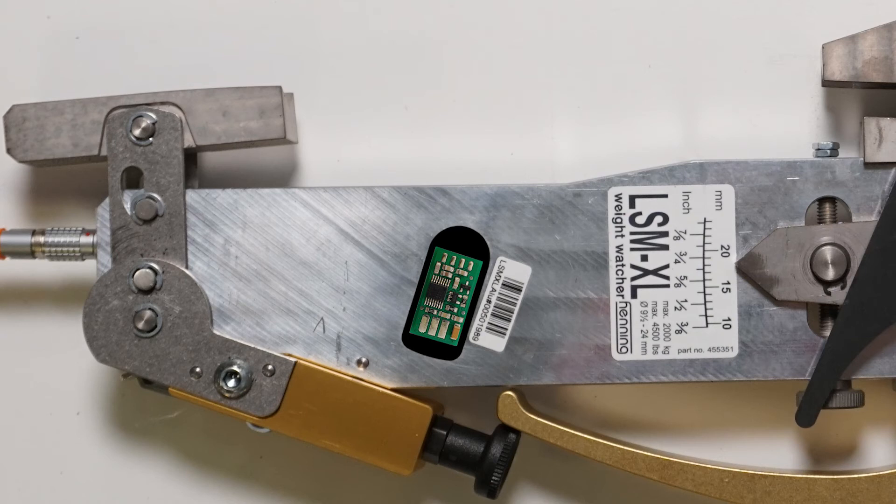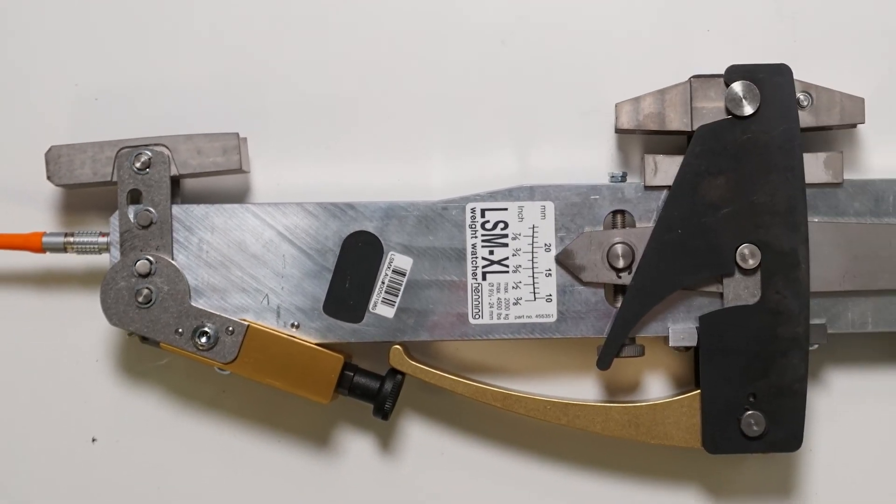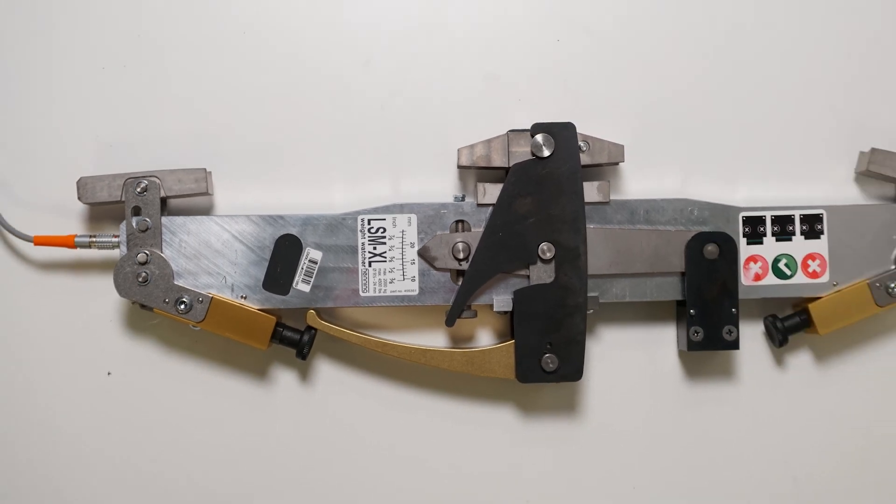The measurement signal is amplified inside the sensor from microvolts to an interference-resistant voltage up to 5 volts. This means that poorly shielded frequency converters, among other things, cannot as easily cause interference in the measurement signal.